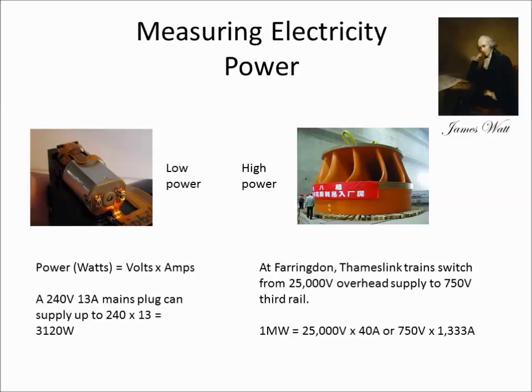But since it's only 750 volts, much less, it needs 1,333 amps at 750 volts to give a megawatt, or 1,000,000 watts. That's a huge amount of current - a lot more even than your car's starter motor uses, which might be only 100 amps. So to supply over 1,000 amps, you need a pretty thick conductor, and those rails along the track are actually pretty thick - that's why they can supply over 1,000 amps.